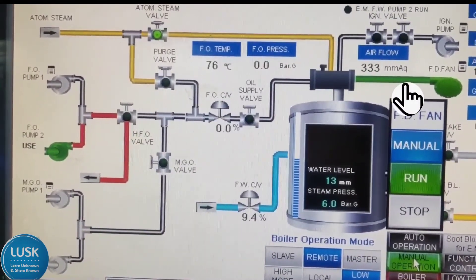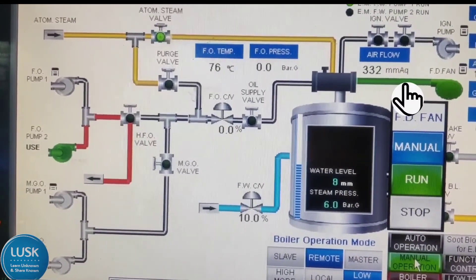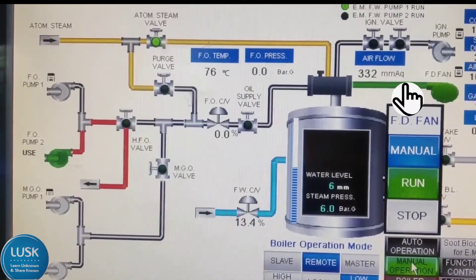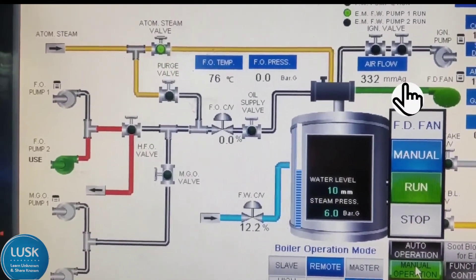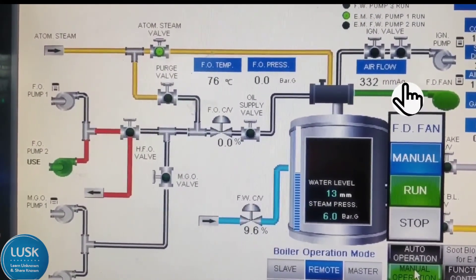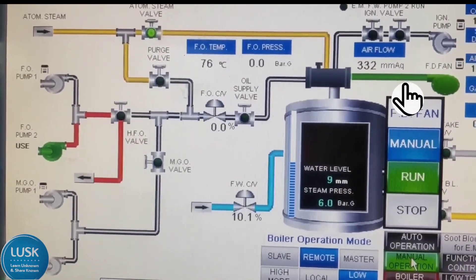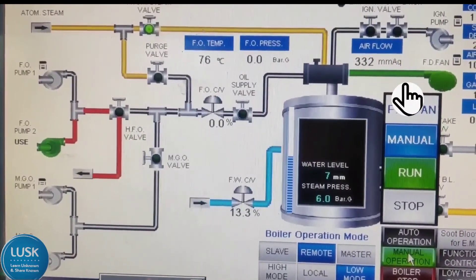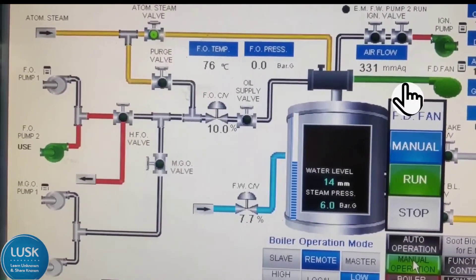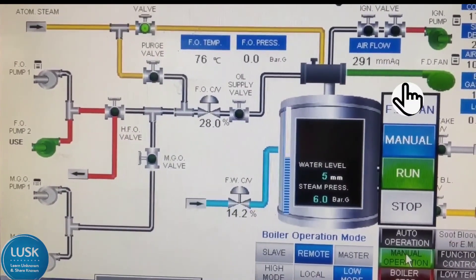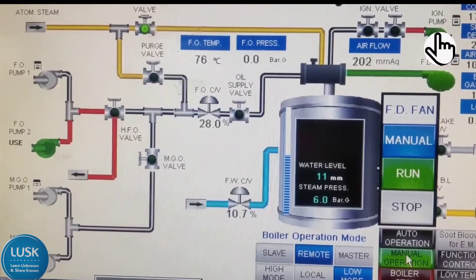Why is purging happening? Because there will be some flammable gases inside, or maybe oil is dripping from a previous firing. To exhaust that flammable gas, when we forcefully compress air inside the boiler, those gases will go via the exhaust. That is why purging is done at each and every initial firing. Now you can see — as soon as the flap started reducing, the ignition pump started.